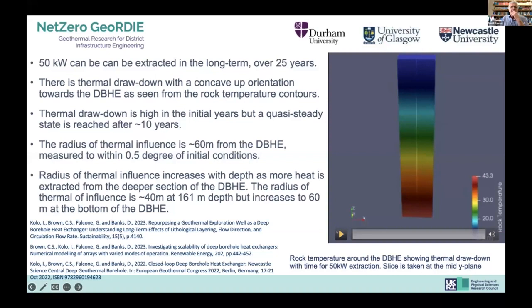Looking at this, it draws down very quickly in the initial years. By 10 years, extrapolated in this animation, you've got this drawdown of temperature and a radius of thermal influence, that is, how far from the hole you have to go before the temperature is the same as if the hole wasn't there. That's about 40 meters at 161 meters depth, increasing to about 60 meters at the bottom of the borehole heat exchanger, because more heat is being extracted. So it varies with depth.